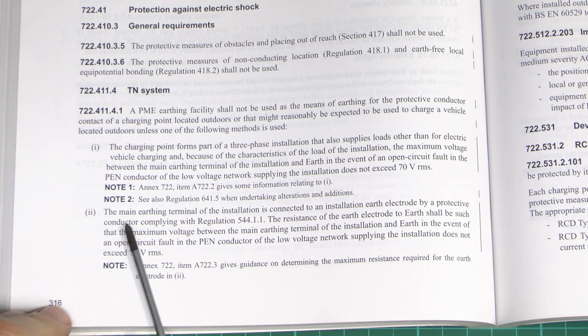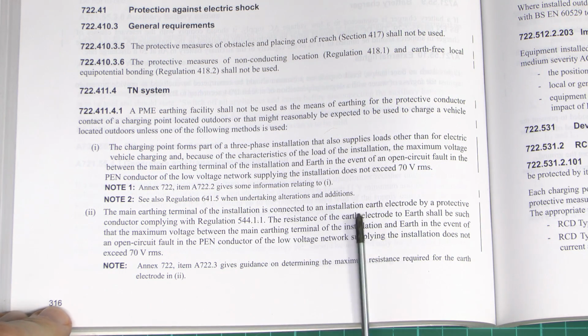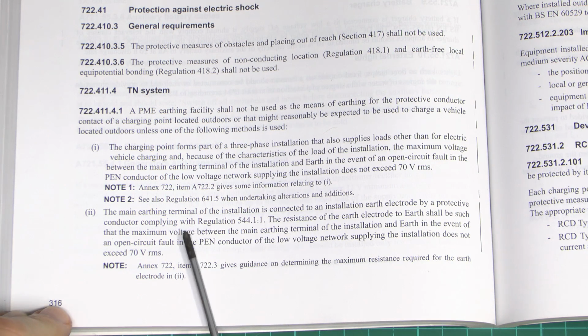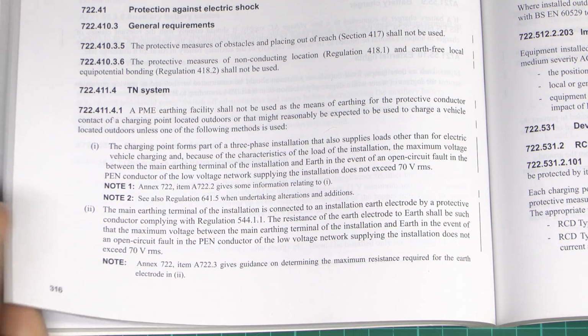The second one here, which is the main earthing terminal of the installation, is connected to an installation earth electrode by a protective conductor. So basically putting in an extra earth electrode or earth rod and connecting it to the supplier's provided earthing terminal. This generally can't be used, and we'll have a look at this in a moment, but the main criteria here is that in the event of the cable having an open circuit fault, the conductor does not exceed 70 volts RMS between the conductor and the actual ground, and we'll look at the calculation later, and basically that's pretty much impossible.